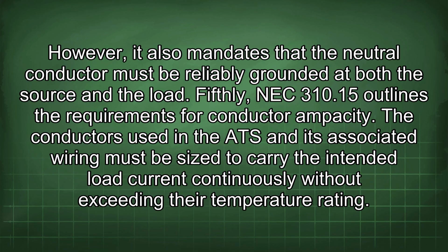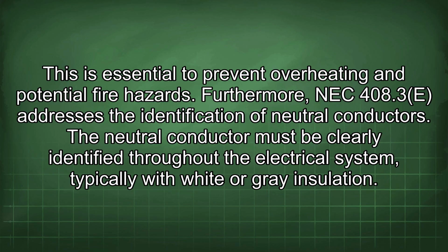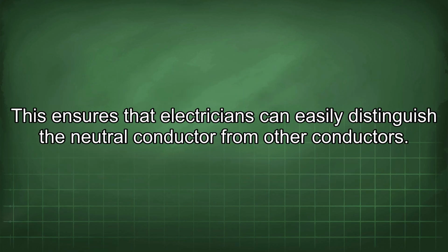Fifthly, NEC 310.15 outlines the requirements for conductor ampacity. The conductors used in the ATS and its associated wiring must be sized to carry the intended load current continuously without exceeding the temperature rating. This is essential to prevent overheating and potential fire hazards. Furthermore, NEC 408.3 addresses the identification of neutral conductors. The neutral conductor must be clearly identified throughout the electrical system, typically with white or grey insulation. This ensures that electricians can easily distinguish the neutral conductor from other conductors.